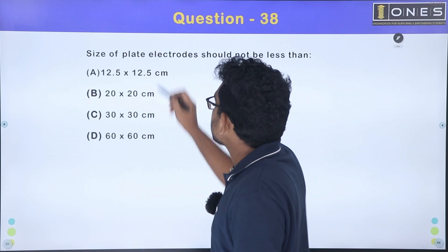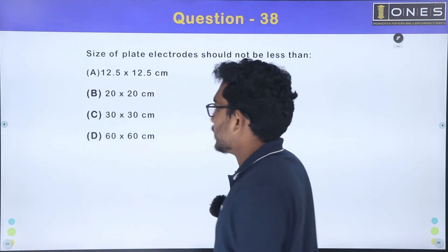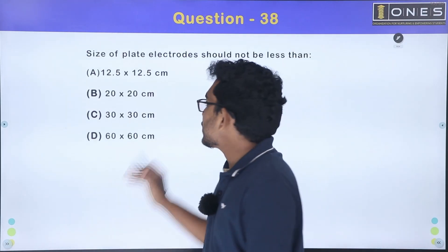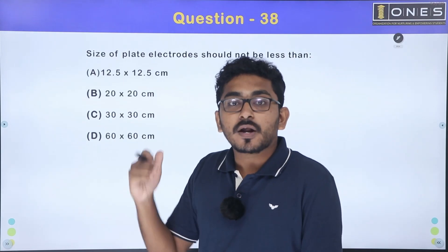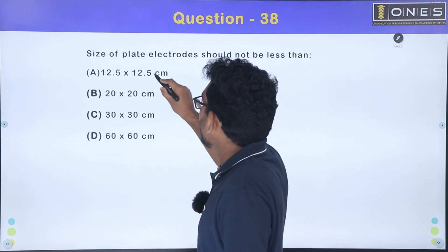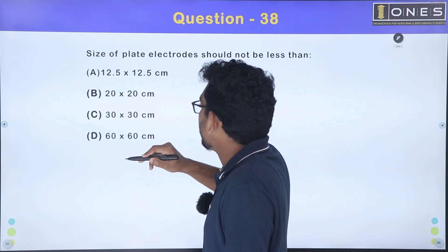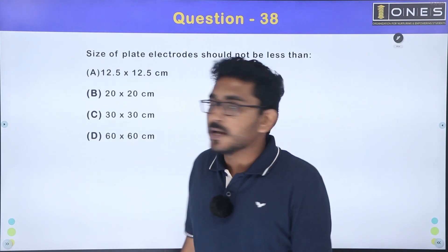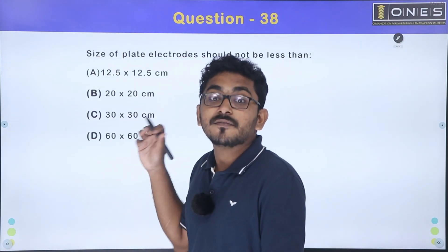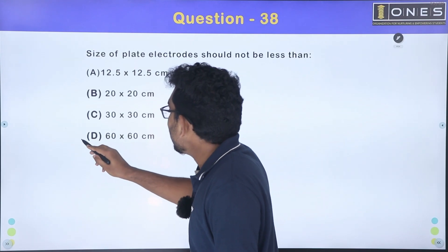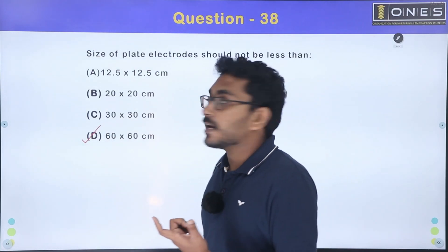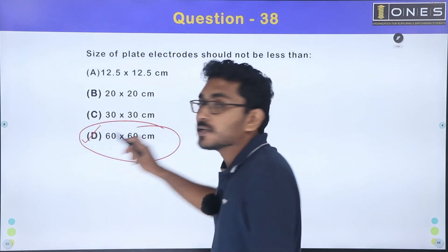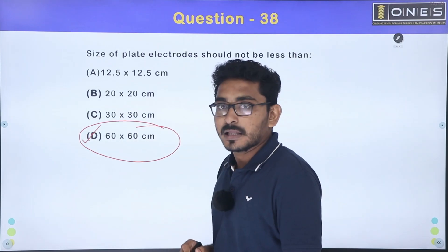Next question: the size of a plate electrode should not be less than what? The options are 12.5×12.5 cm, 20×20 cm, 30×30 cm, and 60×60 cm. Option D — 60×60 centimeter — is the correct answer for plate earthing electrode size.